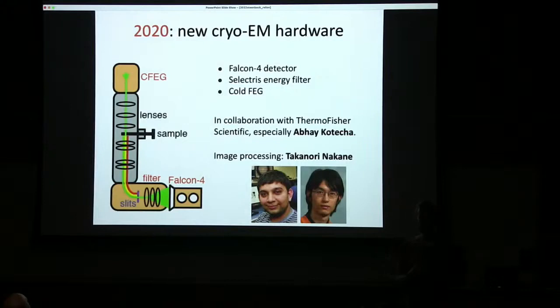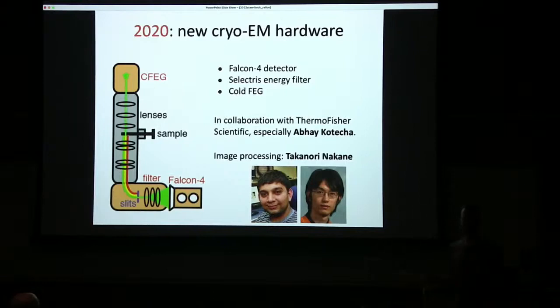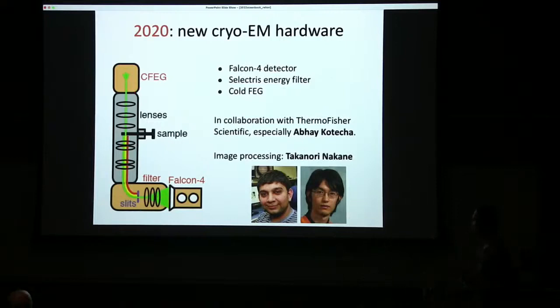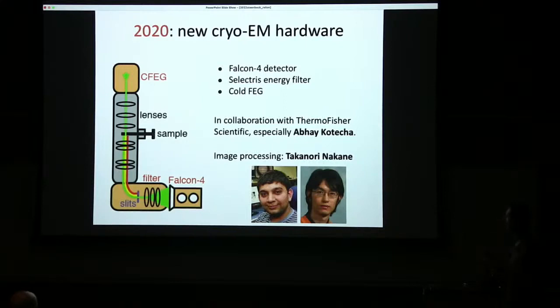In 2020 we collaborated with Abhay Kotecha at the Thermo Fisher factory in Eindhoven. They made some new hardware — and I think you already have some of it here. They did a cold field emission gun, which I'll come back to. A new, more stable energy filter. And the next generation of the direct electron detector, the Falcon 4, with even better DQEs and faster frame rates. We sent Abhay some samples — apoferritin and the GABA receptor — and Takanori Nakane, a postdoc in my lab, processed all the movies that came off this microscope.